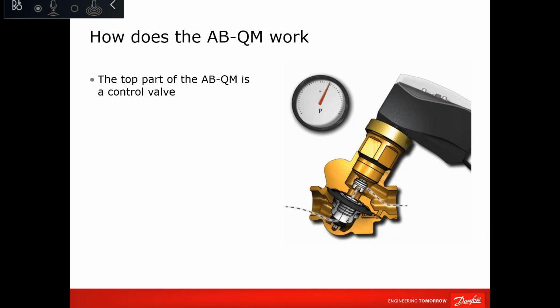All right. And is it possible to verify the flow rate through the control valve using DP, or do you have accurate KV values? For measurement, yes, we can measure like the DRV using the KV methodology and so on. Now, accuracy, it depends. If it is at the higher side, the accuracy will be better. If it is on a lower setting, the accuracy will be less good. But let's say plus minus 10% is the accuracy that you should consider in normal operation. Sometimes it goes to 15 based on how the valve is in the project.